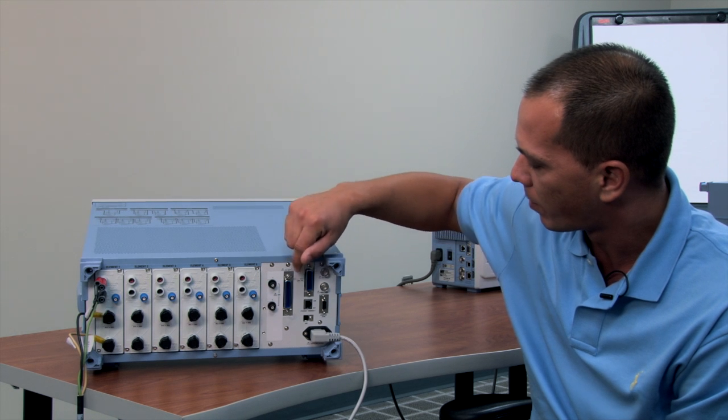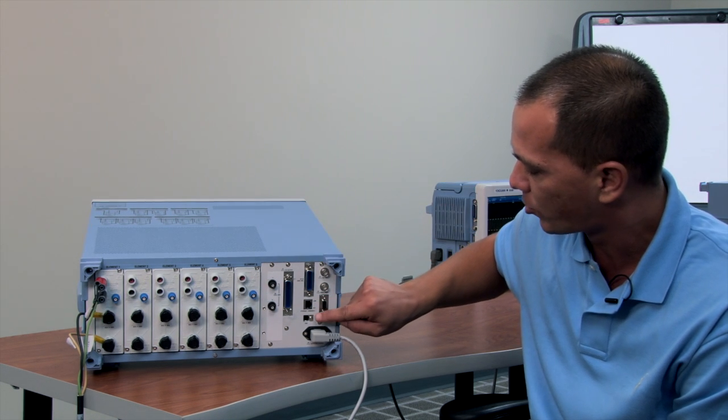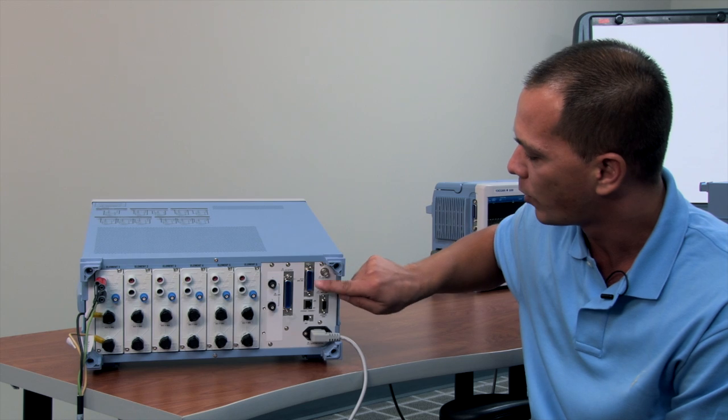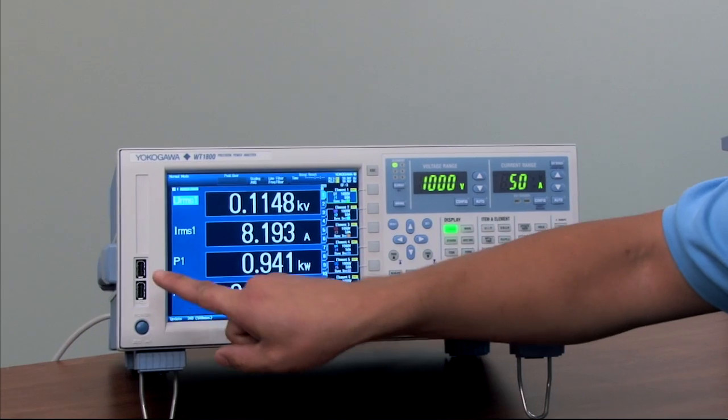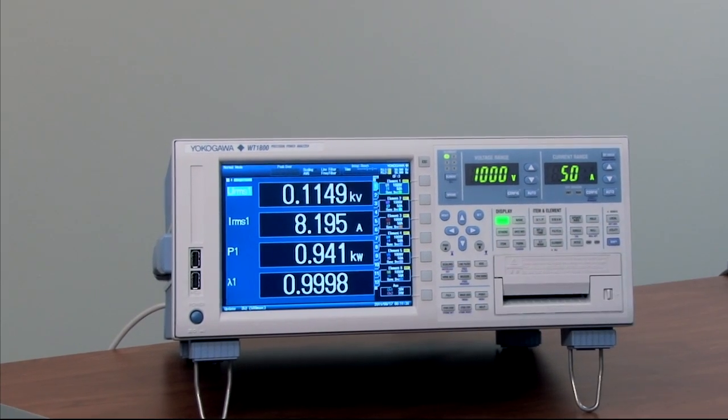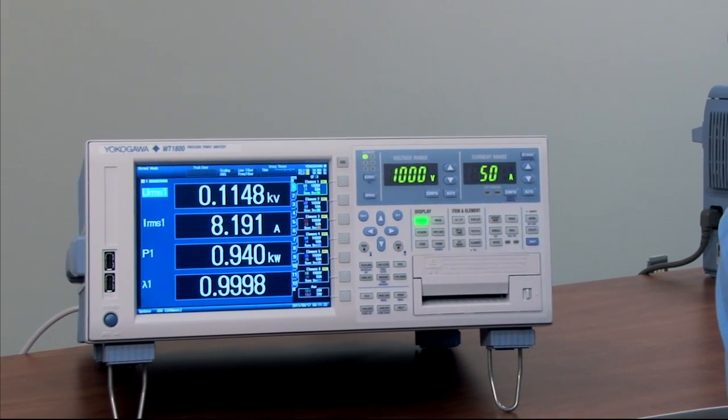The unit comes standard with three different interfaces to communicate with the instrument from a laptop or PC. You have GPIB, Gigabit Ethernet, or USB. There are two additional USB ports located on the front panel for peripheral devices such as USB stick, mouse, or keyboard.